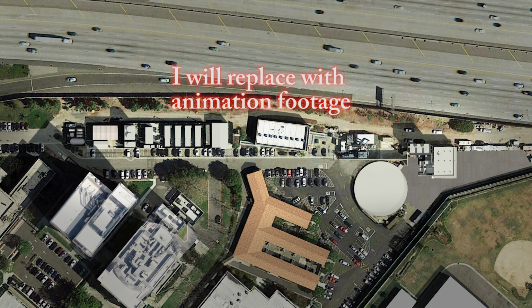Along the north side of the CUP yard, a new 1.5 MW, 12 kV emergency generator will be provided south of the existing generators. The generator will be equipped with a neutral grounding resistor, particulate filter, and fuel storage to match the existing generators. A new outdoor rated 15 kV emergency switchgear section will be provided on the north side of the existing 15 kV modular switchgear enclosure that will accept the feed from the fifth generator, have breakers for emergency feeders, and a control section that will integrate with the existing master controller in the existing emergency switchgear.